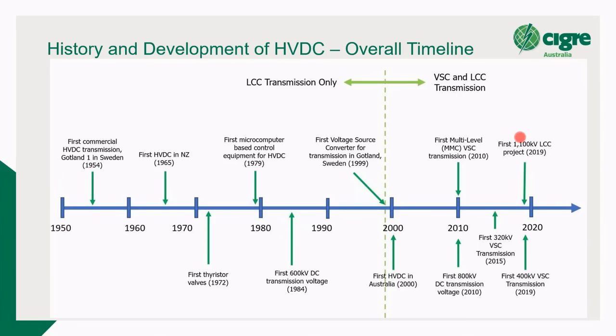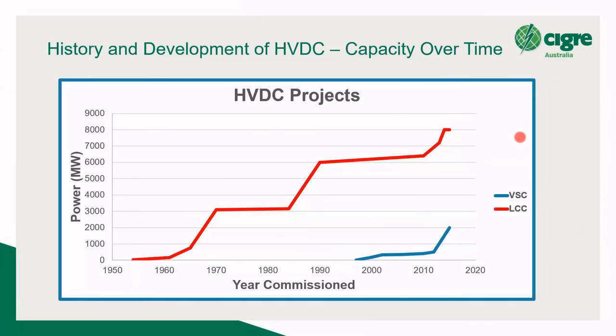So LCC continues to be developed, and this slide here shows, you know, overall capacity now. It's the 1.1 million volt. That's much higher than 8 gigawatts, so I need to update this slide. But basically, this is showing that in the development of VSC, it was relatively low power, but recently it's shooting up to 1,000-2,000 megawatts. Whereas with a couple of spurts, the LCC is sort of leveling out a bit in terms of growth of megawatt value.